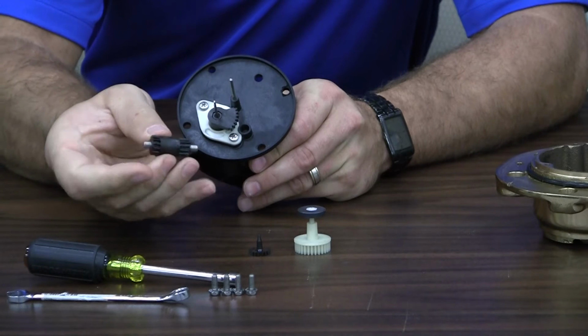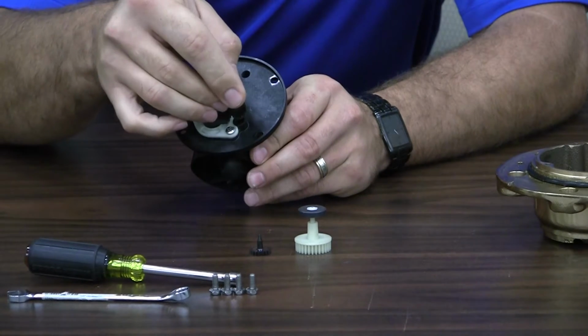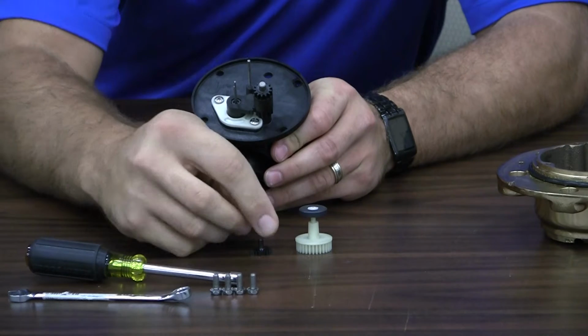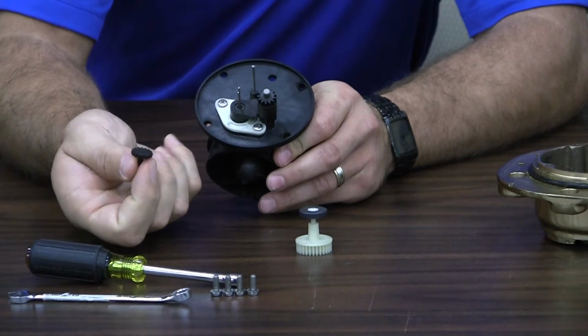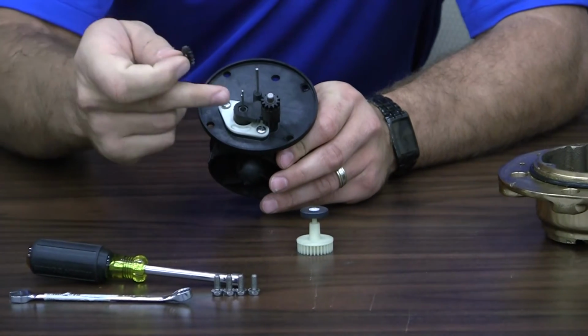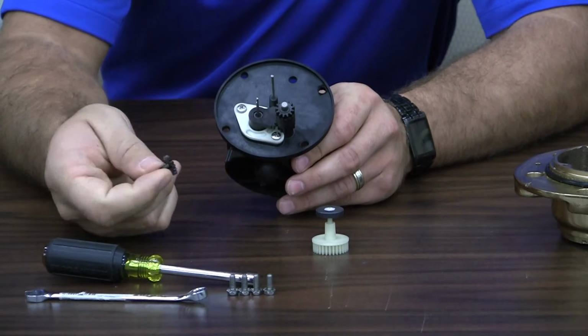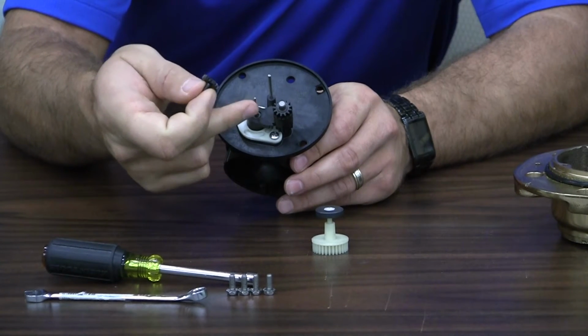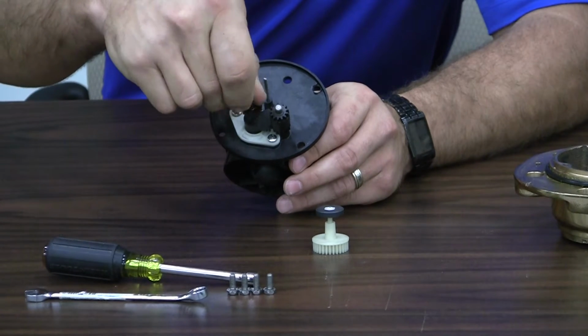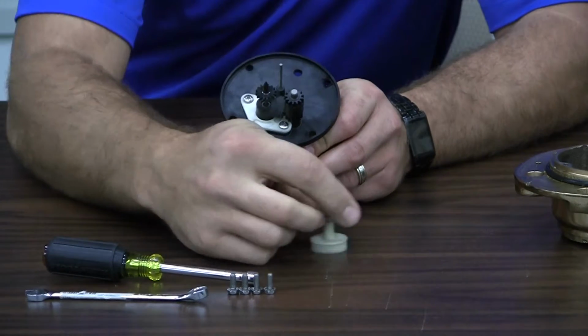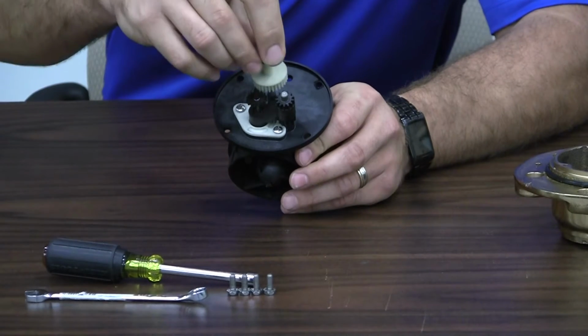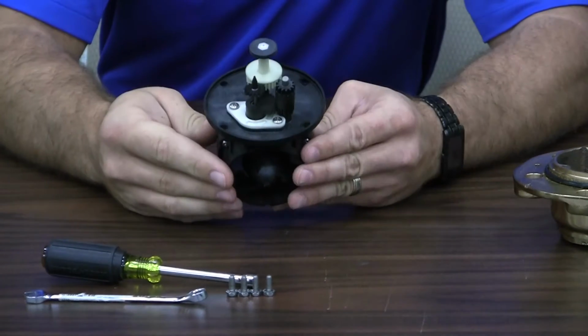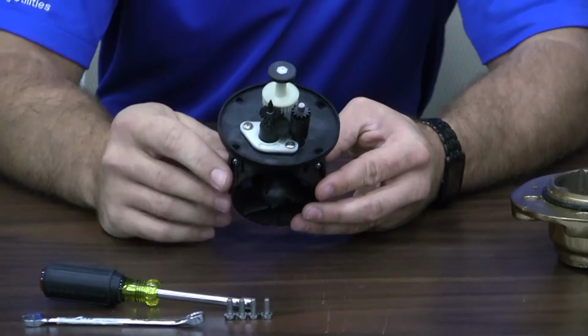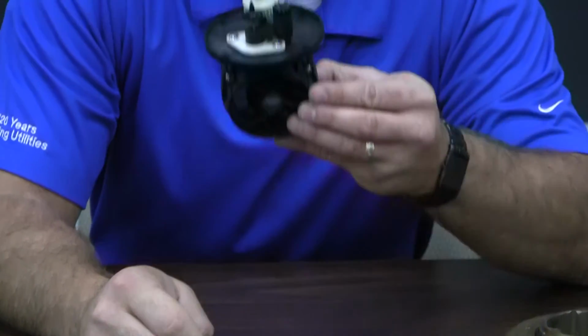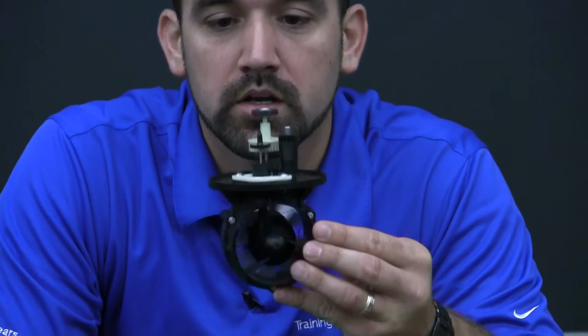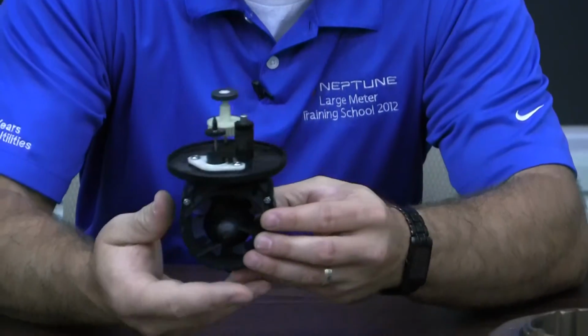So once that's placed, you can see that the gear is towards the calibration gear location. On our calibration gear, we have a long gear and a short gear. We want to make sure that long gear is down towards the turbine element. We have our drive pinion. Our drive pinion has a D-shaped hole inside of it, so it's also going to be on the D-shaped post sitting here. So when you put this on, it'll actually lock in. You can feel it lock. And the last gear we put on is our magnet gear. Now once we have all these gears in place, we should be able to blow through the turbine element again and see all the gears operating smoothly together. So you can see the gears turning on top.